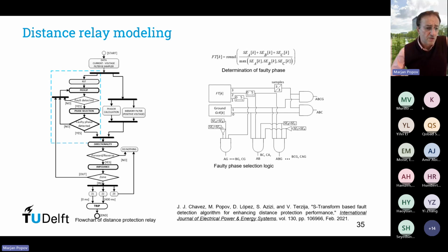So the relay consists of fault detection, faulty phase selection, then directionality, and impedance, which was important to determine the zones, whether it operates in zone 1, zone 2, or zone 3. So I will not go through in this presentation how the relay was developed. It's published in this paper, which is open access and can be read. The faulty phase selector logic that has been applied in this paper is this, and this is how the determination of the faulty phase is achieved by making use of the Stockwell energy for the fault current in each phase.